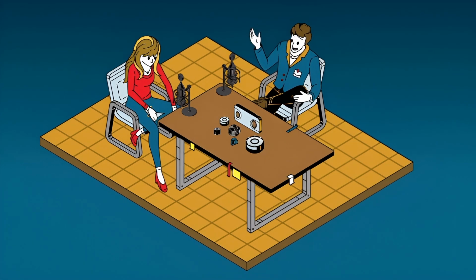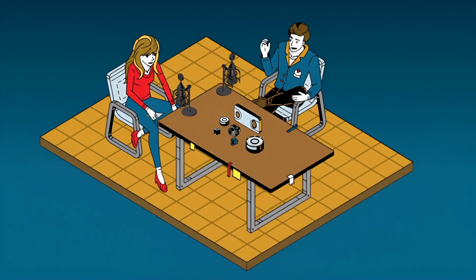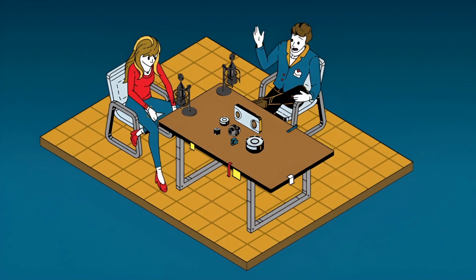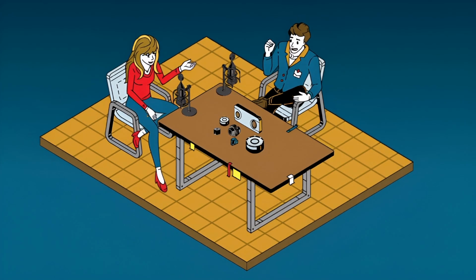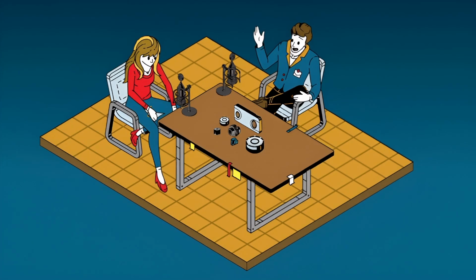The source outlines a fascinating method for preventing this. Engineers build massive test beds filled with simulated alien soil. But to get accurate data on how the wheels perform, they can't just measure the power the motor is putting out. They use an Interface T14 slip ring shaft-style rotary torque transducer, embedded directly inside the hub of the rover's wheel, right alongside the drive motor.